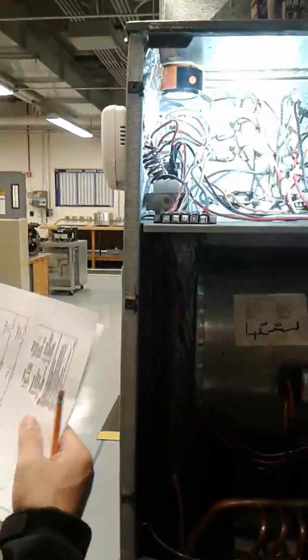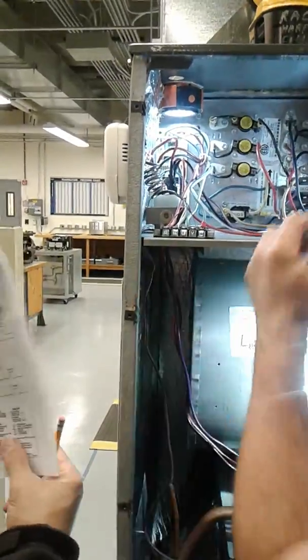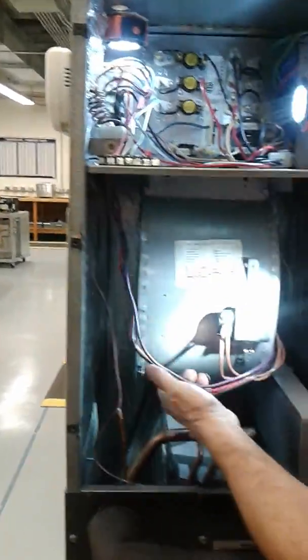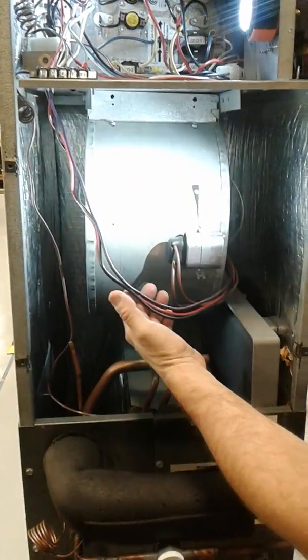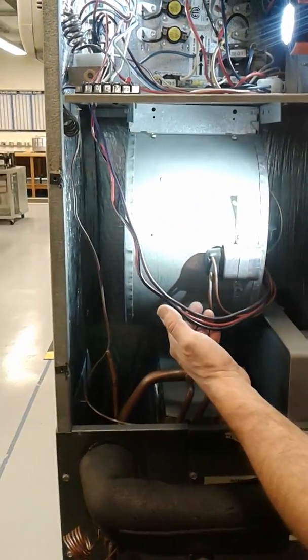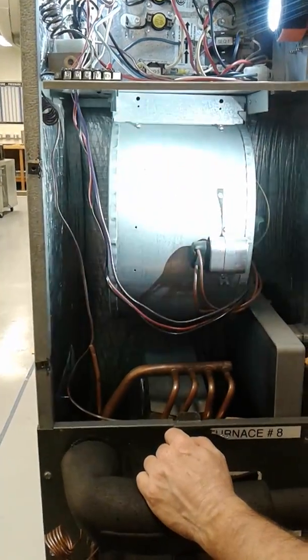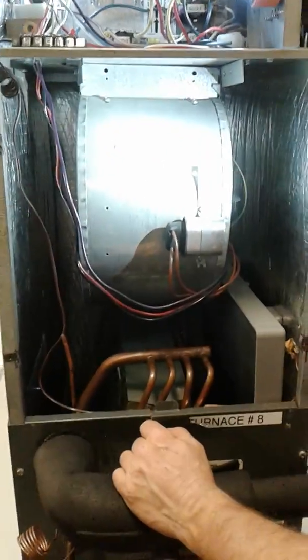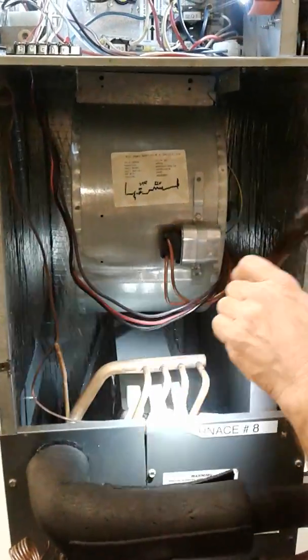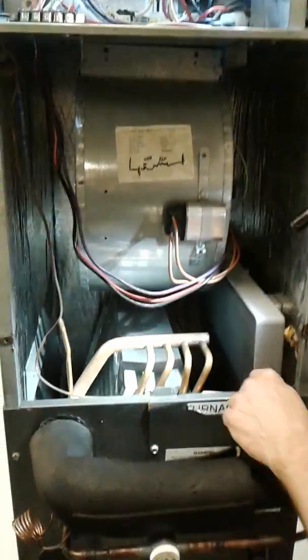Alright, now, down here, guys, okay, is the blower motor. Okay? The blower motor is 240 volts. Okay? It's not 120. Okay? Higher the voltage, lower the amp draw. Okay? And remember I mentioned in class, the evaporator coil's on the bottom.